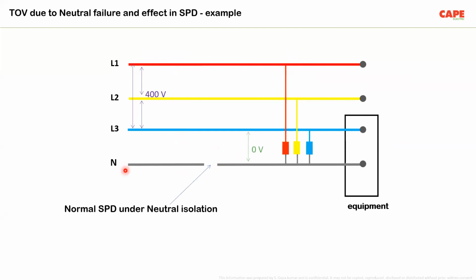Under that condition, the potential between this connected load, a single phase load, and the neutral, of course, becomes zero suddenly. And the potential between that neutral with the other phases becomes 400 volt. Please understand that I am explaining in a very simple way, because we also have some participants who are non-electrical engineers. So between that neutral and the lines, suddenly the voltage is 400 volt due to this neutral disconnection. And what happens is these two SPDs connected between L1 to neutral and L2 to neutral are stressed with a higher potential for a longer duration, and it explodes.